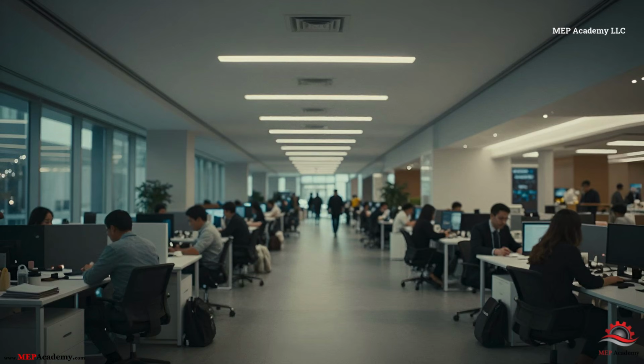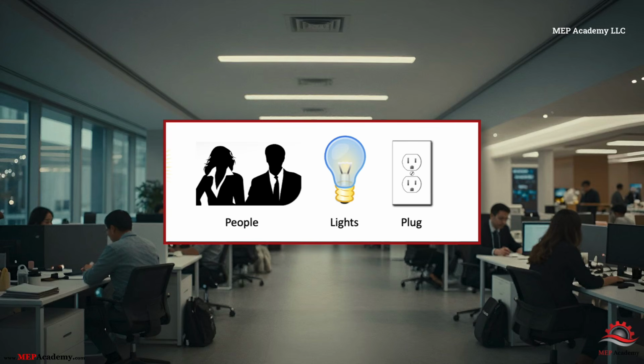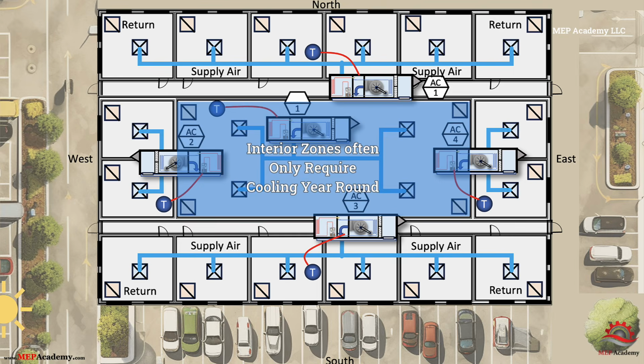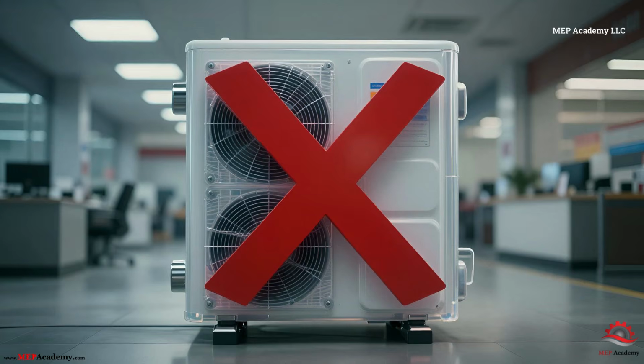Interior zones in commercial buildings such as offices and large retail spaces require cooling all year due to people, lighting, and equipment loads. The key insight is that interior zones often do not require heating, even in winter. Best choice for interior zones: air conditioning systems, chilled water systems, or cooling-only VRF. Installing a heat pump here would add cost and complexity with little to no benefit.